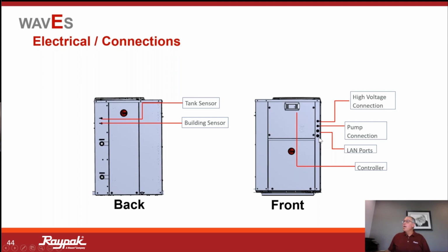On the front of the unit, you have what looks like knockouts, but they are grommets. And here's where we can bring in our power and our line voltage, if you will. We'll talk about LAN, local area network ports. We're going to be using those when we're tying multiple units together. We'll just consider that to be our cascade wiring, a term that you're probably familiar with, right? So again, more to follow, but just a glimpse into the cabinet where you're going to find your tank sensor and building sensor, as well as on the front where you're going to find your line voltage for your circulator and your primary power.